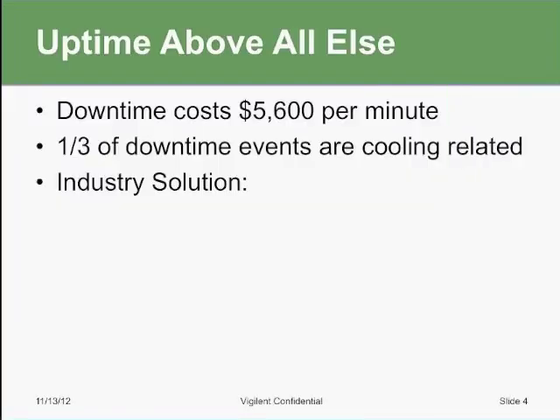So Dennis, Nicole, and I will be discussing the operational challenges that data centers face for ensuring uptime in their facilities around the clock. As data centers are becoming larger in their sheer size, the IT equipment and environment is becoming more dynamic, and as the equipment in those facilities on the IT side and the cooling side are becoming more sophisticated, it's becoming more and more difficult to avoid downtime incidents. And downtime costs about $5,600 per minute, and actually in financial institutions, that number is closer to $5,600 per second. And about one-third of downtime events are cooling related, and that's going to be the focus of our discussion today.